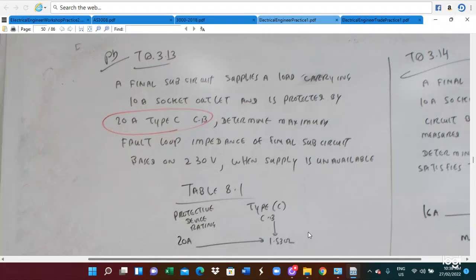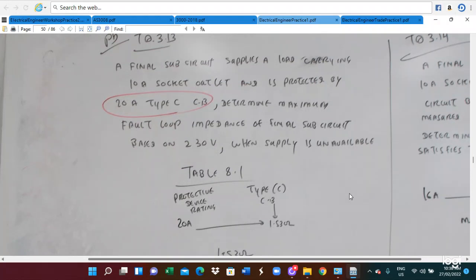Today's lesson covers an engineering practice problem. A final circuit consists of a socket outlet with a 10A rating and is protected by a 20A Type C circuit breaker. We are required to determine the maximum earth loop impedance for the final circuit based on the AS3000 standard when supply is unavailable. The socket breaker is Type C and the rated current is 20A.